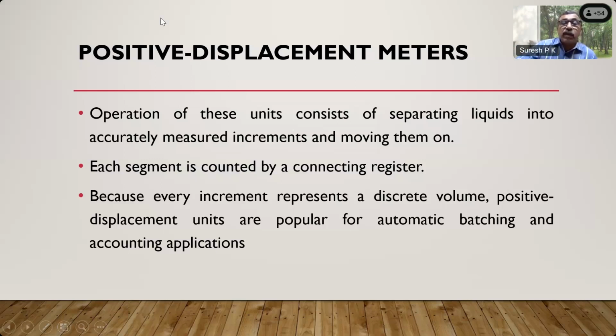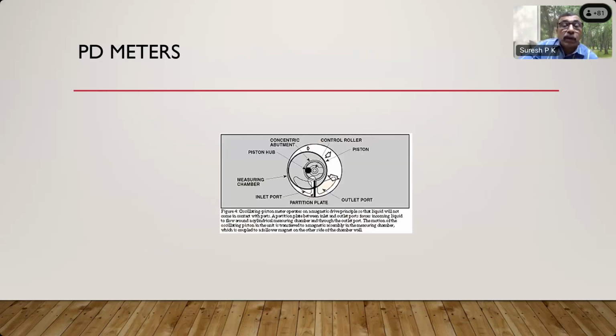Each segment is counted by connecting into a register, which is a very common meter which is used in petrol bunks, oil, ATF transfer, and all those things. Positive displacement are used. I think most of the legal metrology officers would have encountered this flow meter many times. So there are different kinds of PD meters available. One is... I won't go into the details because the time does not permit that.